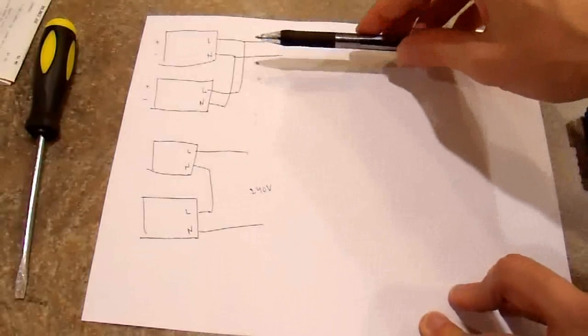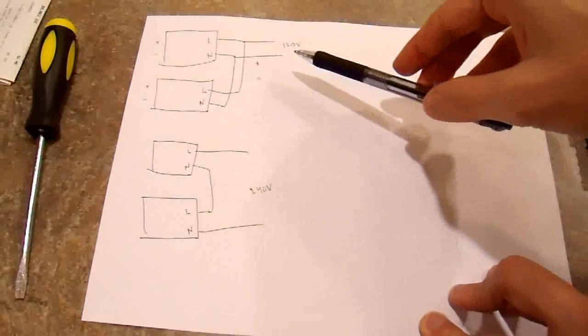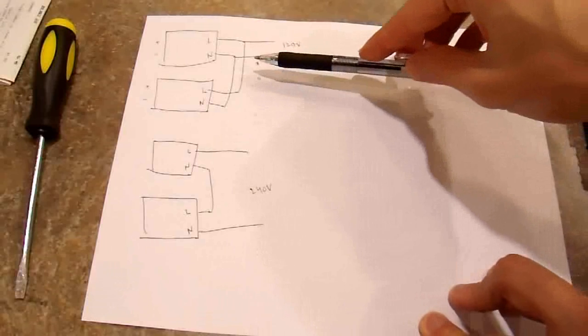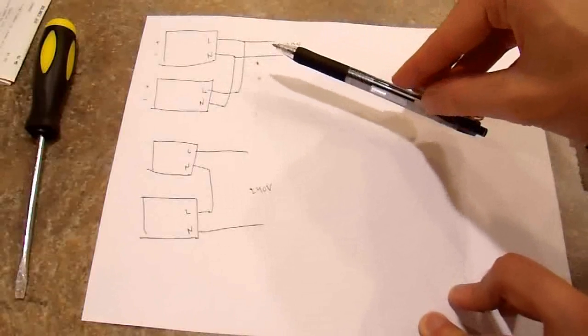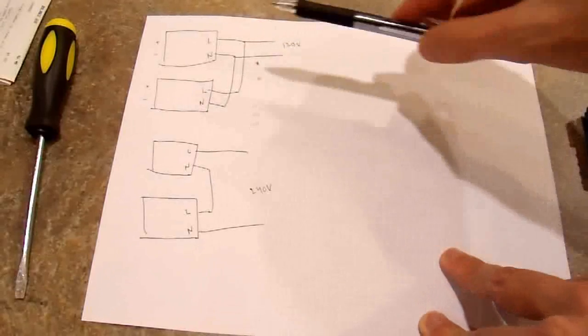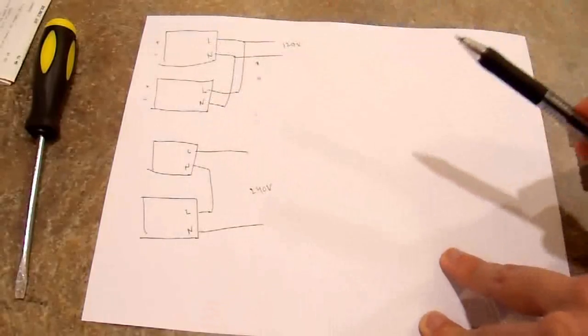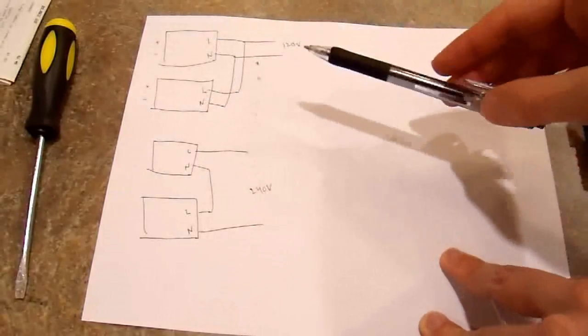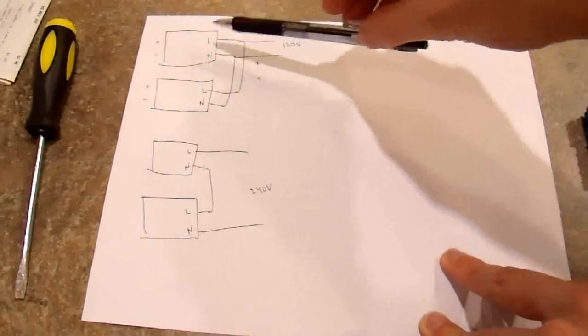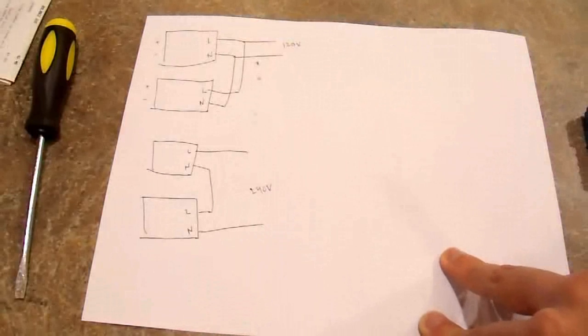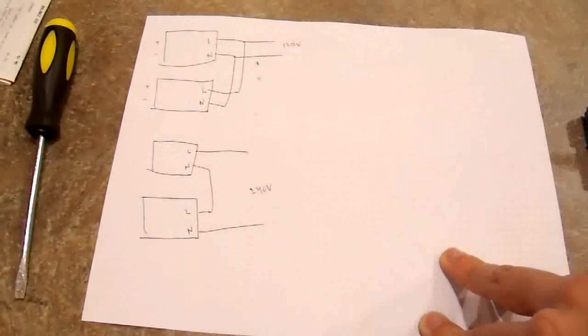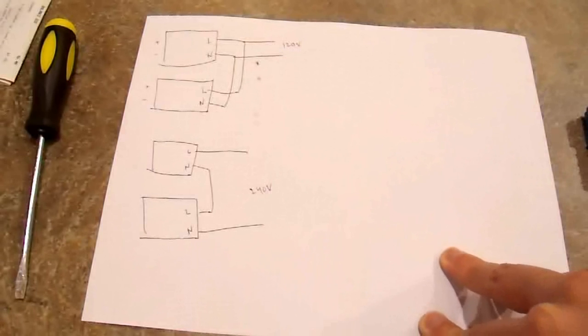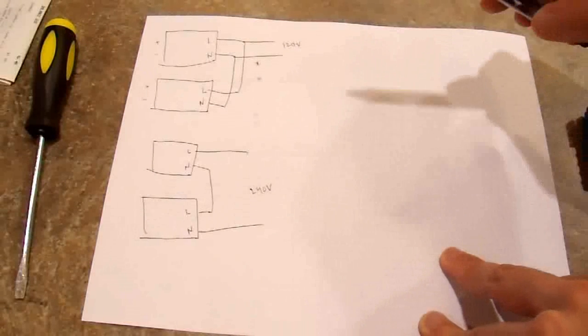This is the method that most people want to use because they don't want to double the voltage. However, this is also very difficult to accomplish from an engineering perspective. You need to have both of them perfectly in phase in order for this to work. Otherwise, if you try to do this with most inverters, you'll end up with zero inverters instead of two like you had before, because they'll destroy each other or blow fuses, best case.